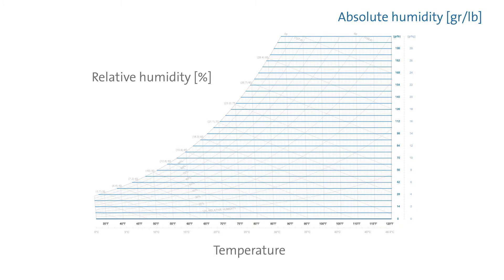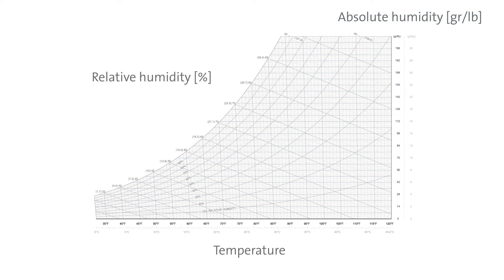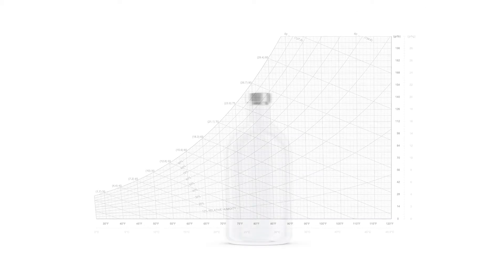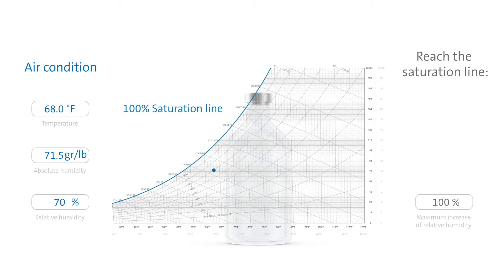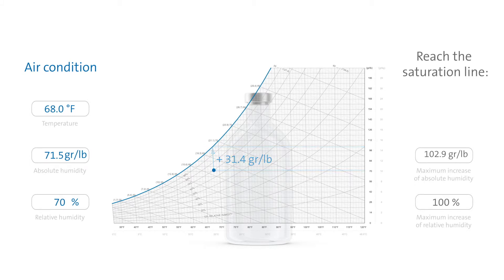So now, what can we say about an air condition with an established temperature, absolute humidity and relative humidity? Let's assume we have a flask containing air at 68 degrees Fahrenheit, 71.5 grains of water per pound of air, and 70% relative humidity. For a start, we know that the air is already very humid and can only absorb 30% more humidity. We also know that the air will reach the dew point line if absolute humidity increases by 31.4 grains of water per pound of air.